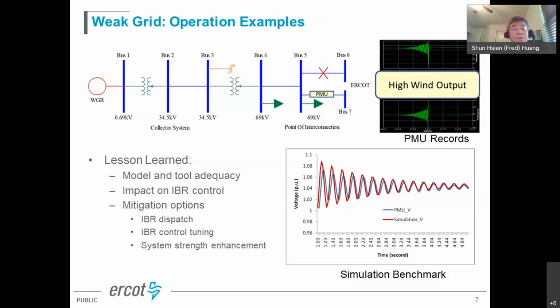A quick overview: we had a wind project connected to the 69 kV system, and through two transmission lines connected to the ERCOT main system. We had a maintenance outage between bus 5 and bus 6, and at that moment the project became radially connected to ERCOT through a single 69 kV circuit. We also have a PMU at the POI location. The top right shows the actual PMU recording during high wind output conditions.